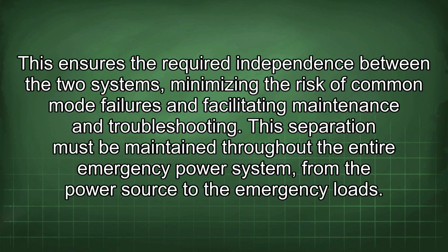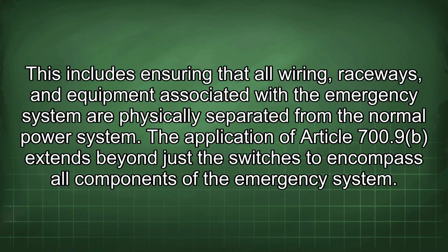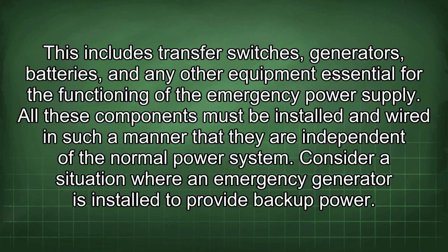This ensures the required independence between the two systems, minimizing the risk of common mode failures and facilitating maintenance and troubleshooting. This separation must be maintained throughout the entire emergency power system, from the power source to the emergency loads. This includes ensuring that all wiring, raceways, and equipment associated with the emergency system are physically separated from the normal power system. The application of Article 700.9 extends beyond just the switches to encompass all components of the emergency system. This includes transfer switches, generators, batteries, and any other equipment essential for the functioning of the emergency power supply.